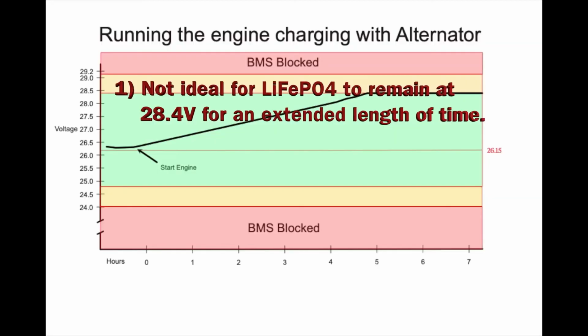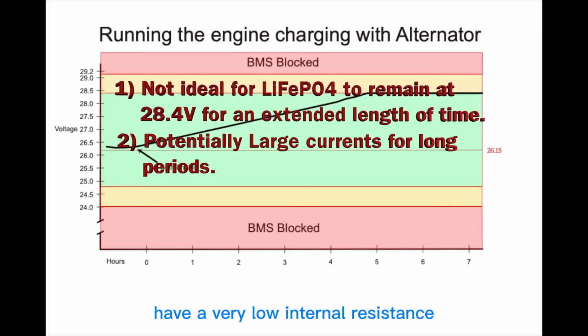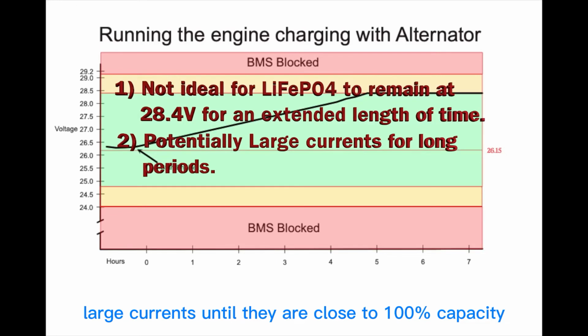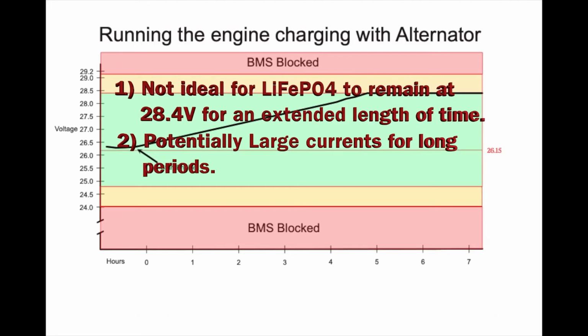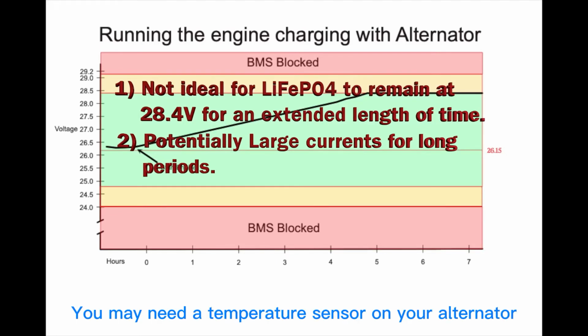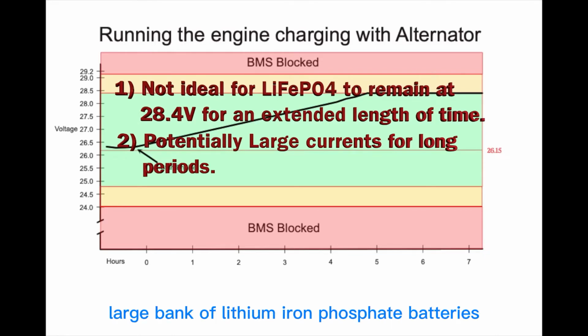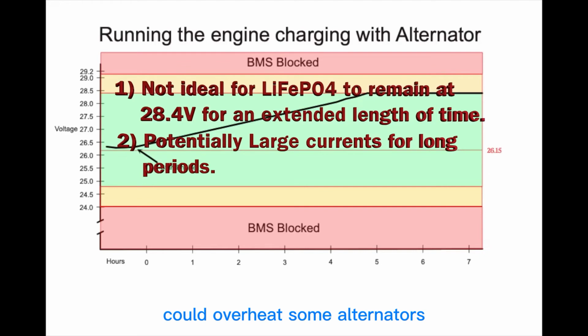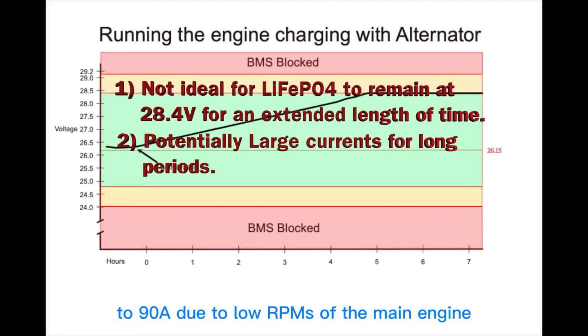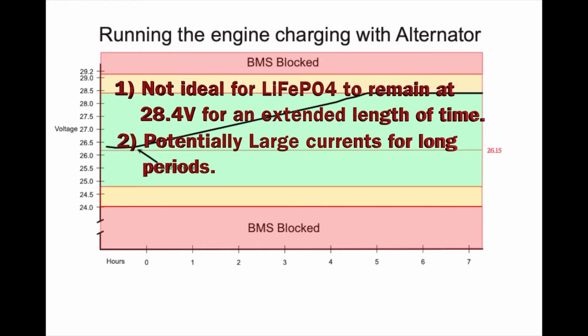2. The lithium iron phosphate batteries have a very low internal resistance, and they can take on large currents until they are close to 100% capacity. You may need a temperature sensor on your alternator because charging a large bank of lithium iron phosphate batteries could overheat some alternators. Aquarius has a 200 amp alternator that is regulated to 90 amps due to low RPMs of the main engine, so this is not something I worry about.